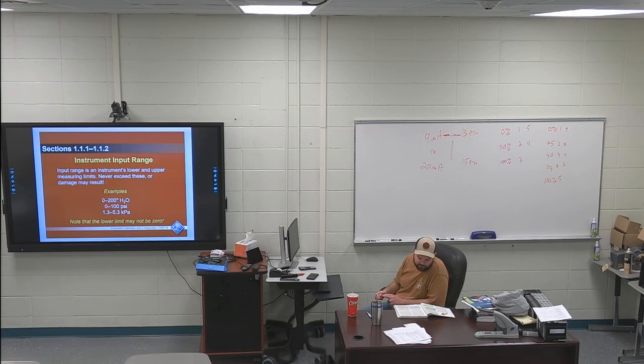point of that span. Another example is the same instrument has an output range of 3 to 15 psi. It has a span of 12 psi. 15 minus 3 is 12. But since the 0 point is 3 and not 0, a 50% output will be 9 psi. 12 times 50% is 6, plus 3 is 9. So 9 would be 50%. Does that make sense? Or is that too confusing?